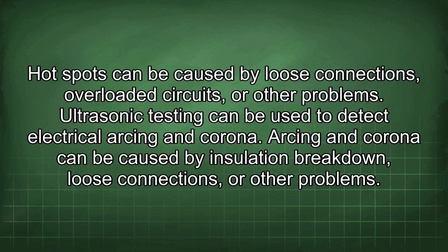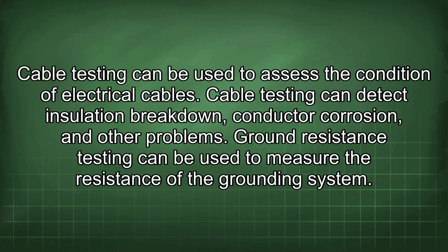Ultrasonic testing can be used to detect electrical arcing and corona. Arcing and corona can be caused by insulation breakdown, loose connections, or other problems. Cable testing can be used to assess the condition of electrical cables. Cable testing can detect insulation breakdown, conductor corrosion, and other problems.